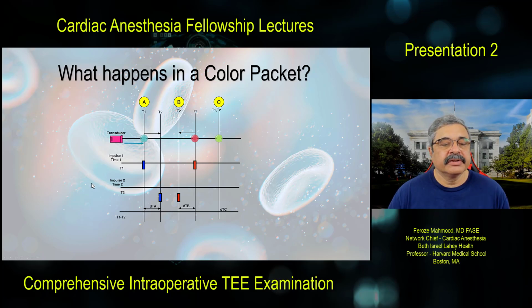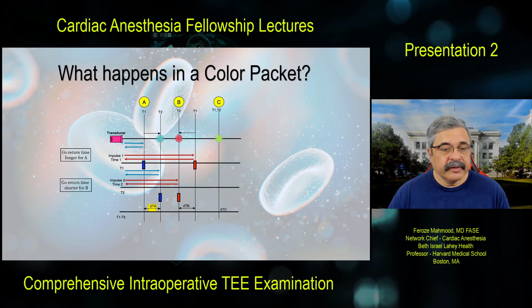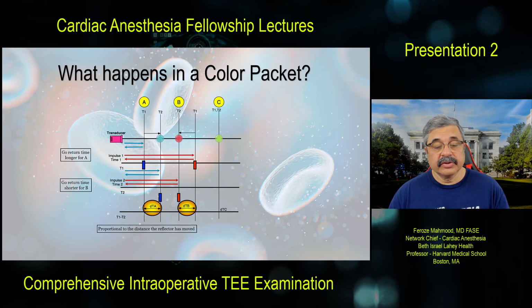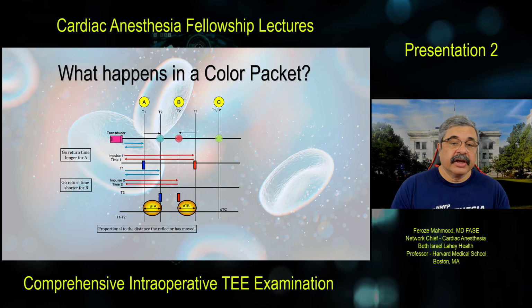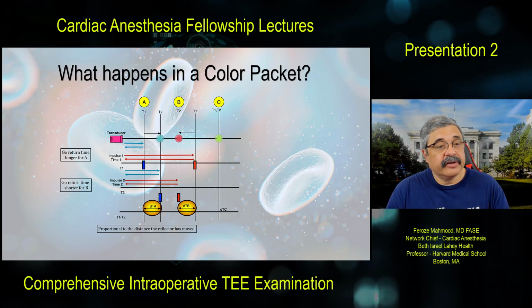Now, the go return time for RBC-A at this time is this much. When it moves to location 2, the go return time for RBC-A becomes longer. The initial go return time for RBC-B is this much, but when it moves from location 1 to 2, this is the go return time, and it is shorter. The difference in time between location 1 and location 2 for RBC-A and B is proportional to the distance the reflector has moved. The time it takes to travel from one location to the other is proportional to the distance traveled, and that essentially is the Doppler shift, and this is how it is calculated.